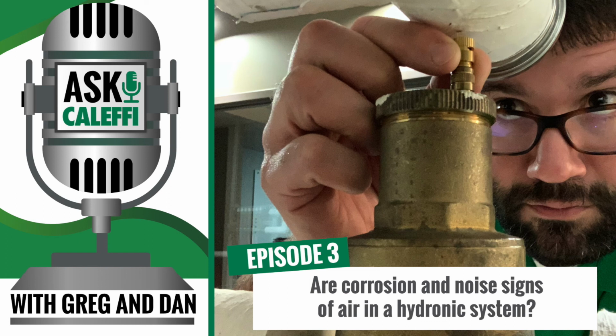Bigger models, the flange models, the steel body models, you've got a very serviceable air vent again, where you can get a cover and float or pull it apart and clean it. You can pull the vent out. We do not offer replacement mesh for those. No, it's very rare that one goes bad. You have to have a lot of problems with fluid quality. Right. And usually that would be debris buildup as well.